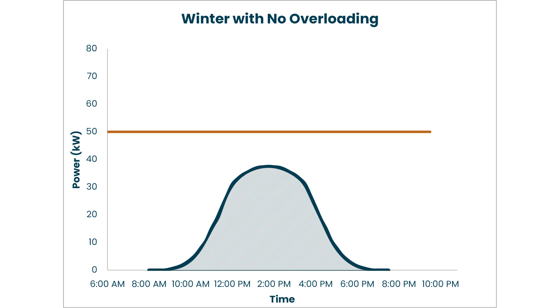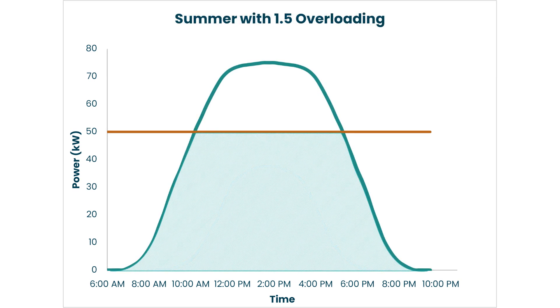Let's consider another example with a 1.5 DC to AC ratio. In the summer, on a perfect day, we can output 50 kilowatts now for 7 hours, hitting that 50 kilowatt limit sooner and maintaining it longer. This does result in significant what we call clipping, which is the unused energy above the inverter's capacity — essentially lost energy.